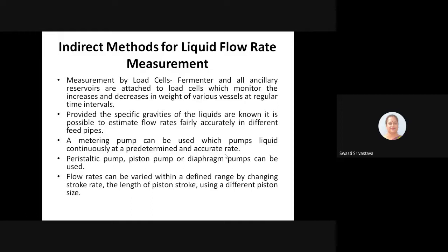In a peristaltic pump, the liquid is moved forwards gradually by squeezing a tubing held in a semicircular housing. A variety of sizes of tubes can be used in different pumps that produce different known flow rates over a very wide range. And suspensions can even be handled since the liquid has no direct contact with the moving parts.